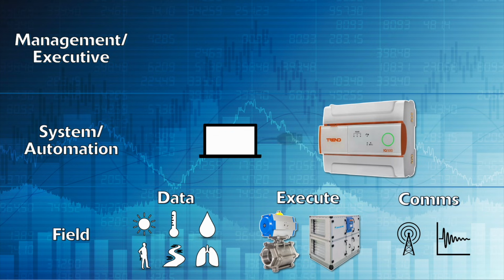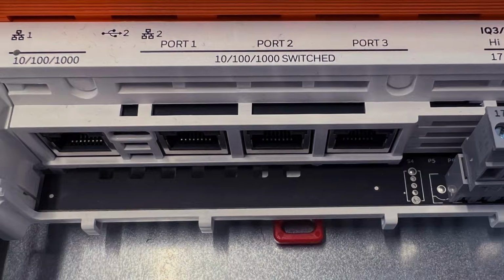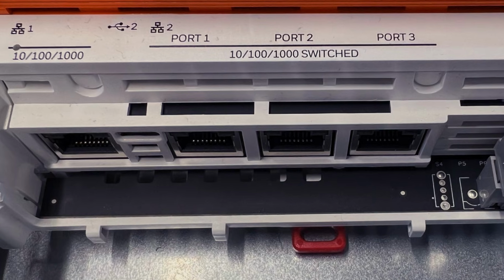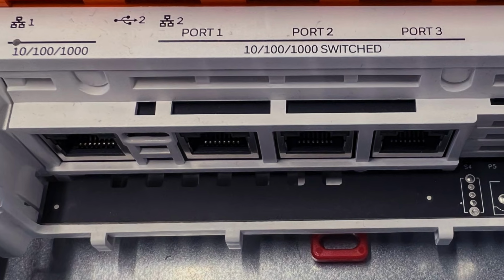The parameters and settings on the DDCs can be controlled and adjusted in a couple of ways. The first is by plugging a dedicated operator terminal into the DDC and programming it from there. Modern DDCs will connect to a variety of devices via either a hardwired network cable or a wireless Wi-Fi connection, with apps and software that will allow you to connect, control and modify the program that controls the building, as well as overriding the system if necessary.